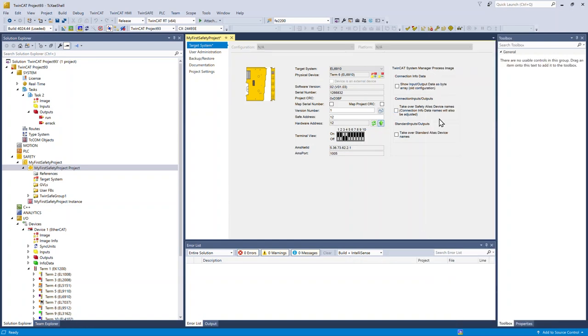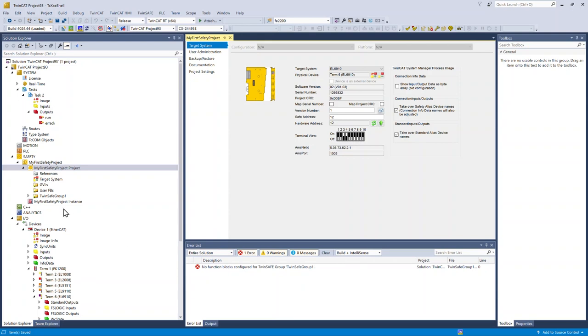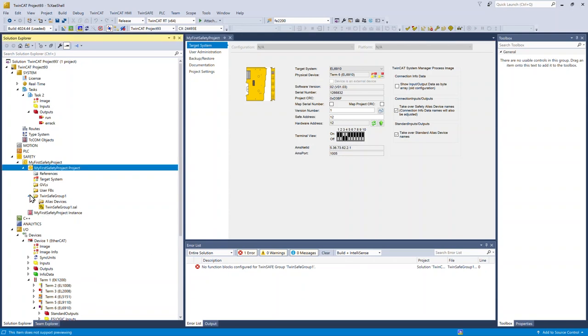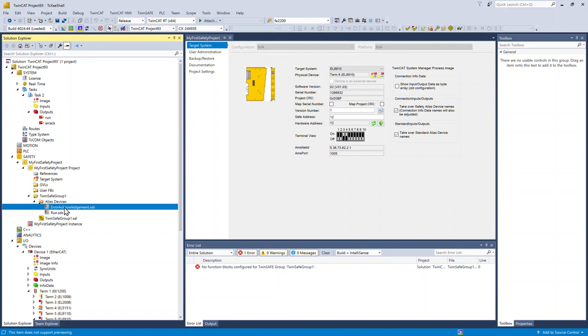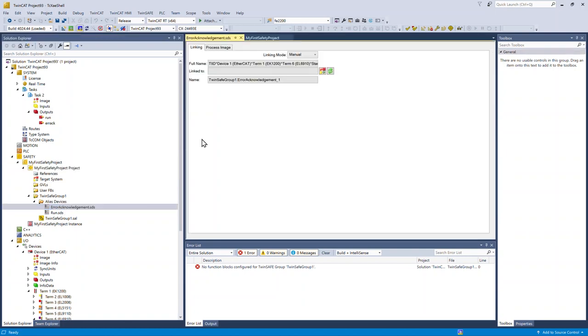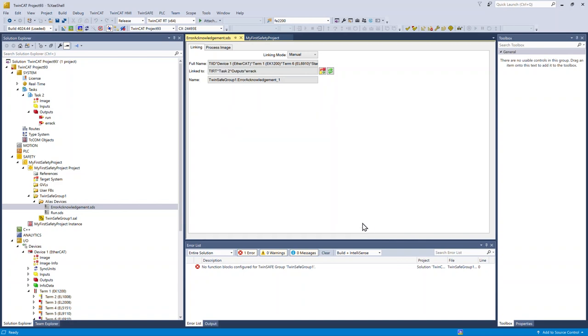Good practice is to take over safety alias device names and standard alias device names. These are the variables that are going to appear under the IO tree, and rather than just having numbers, they'll actually get a name. Alias devices are how TwinSafe interacts with the outside world. The first two that we see here are error acknowledge and run bits that we're going to use to connect to the task that we created earlier. This really means that the rest of TwinCat can still interact with what's going on in the safety project.